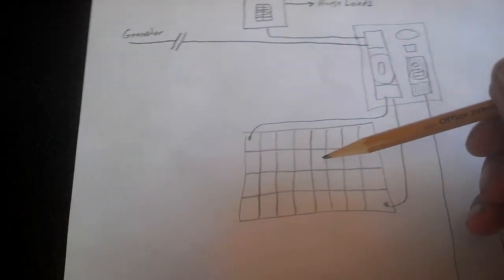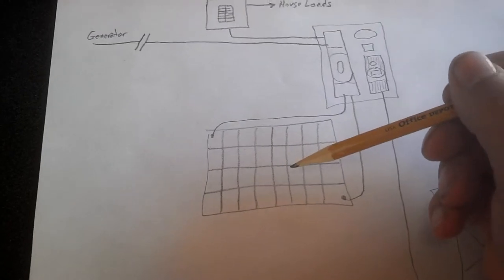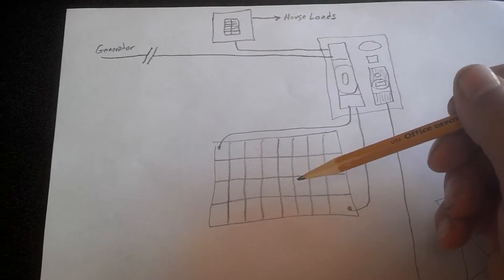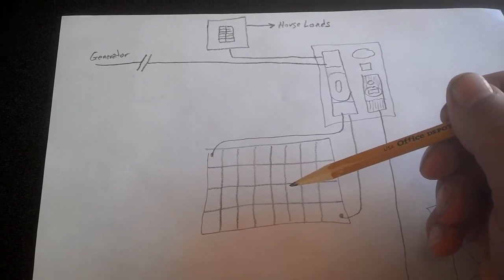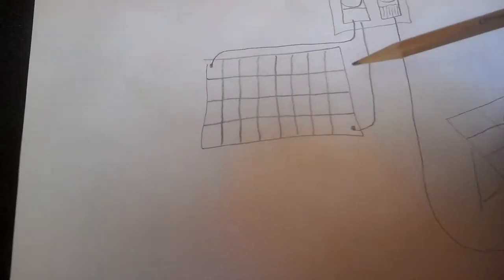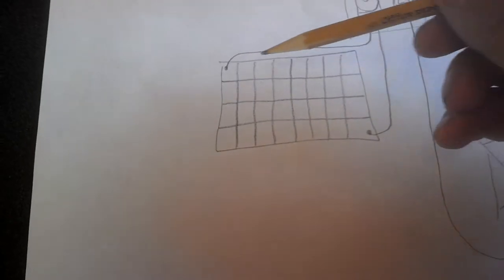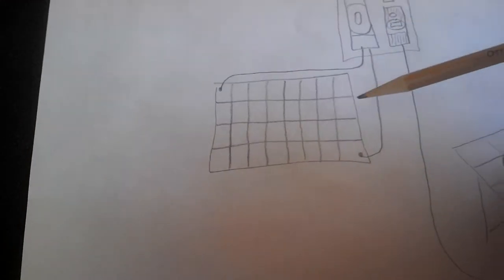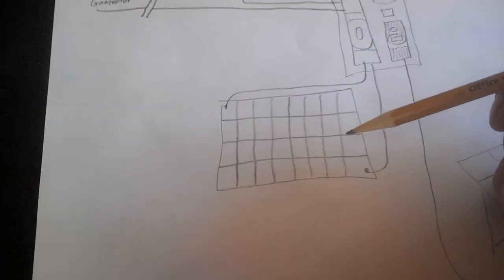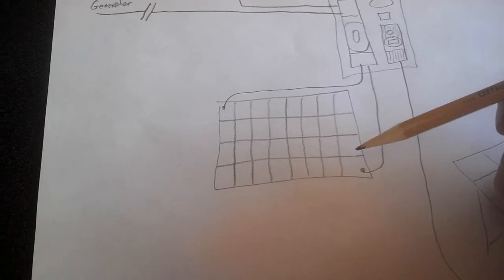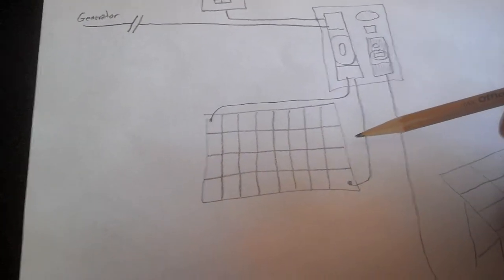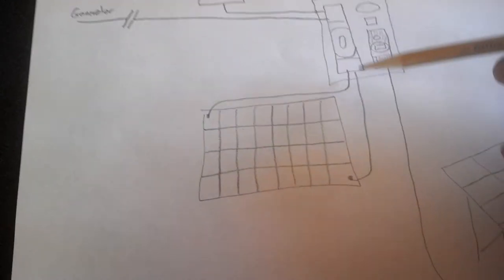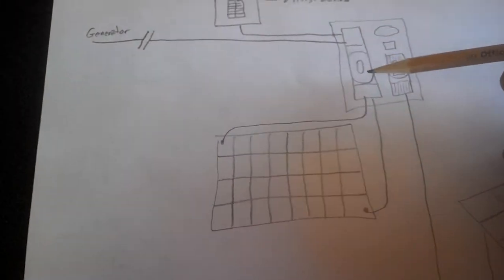Then over here we'll have our battery bank consisting of 32 Trojan T105 RE batteries at 225 amp hours apiece. There'll be four rows of eight batteries apiece, making a 48 volt battery bank that will come into the inverter.